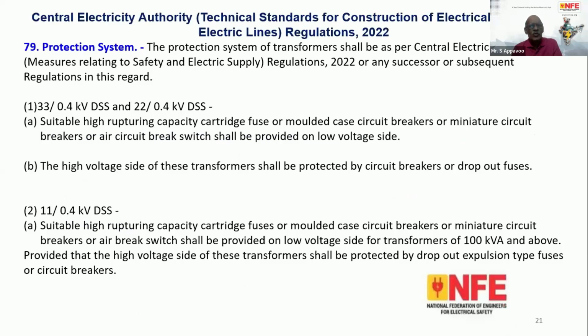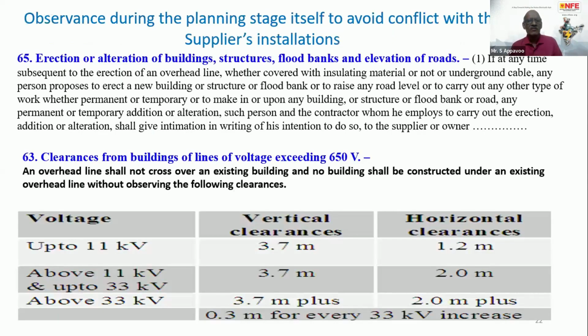Then, for the supplier, there is one more regulation which specifies technical standards for construction of electrical plants and lines. Under regulations 2022, there is a clear provision for the protection system of transformers, that is, distribution substations. So as per regulation 79 of this provision, there should be a circuit breaker or high rupturing capacity cartridge fuses. And for the 11/433 volt distribution substations also, there should be some provisions. We should see whether these are complied with or not during the connection time itself by the supplier.